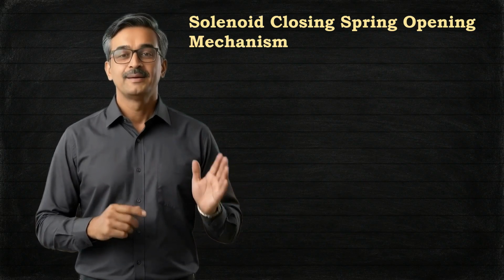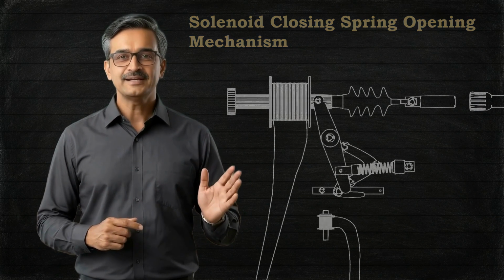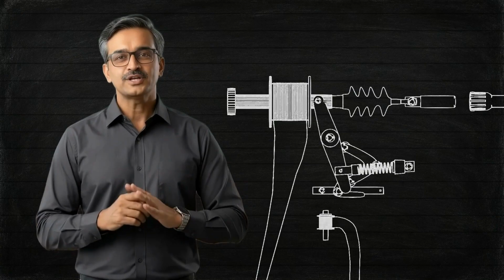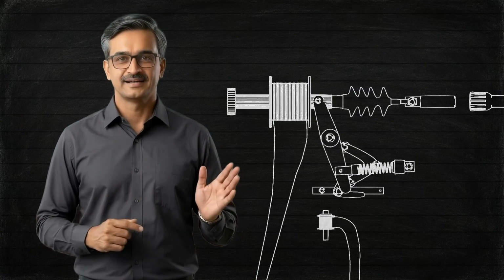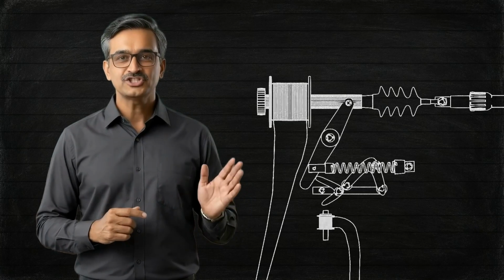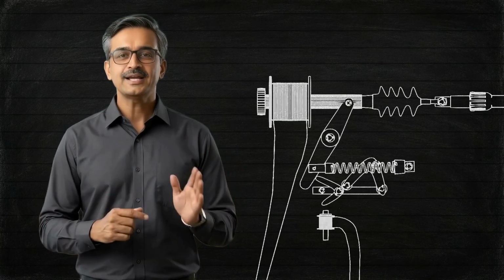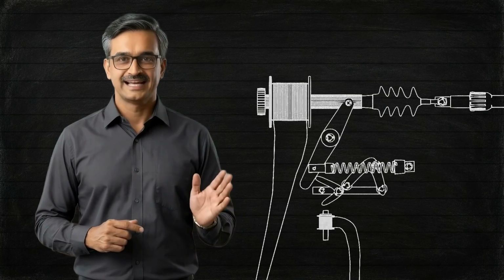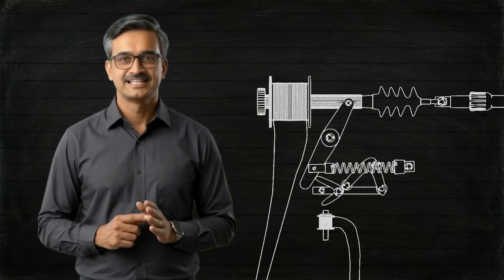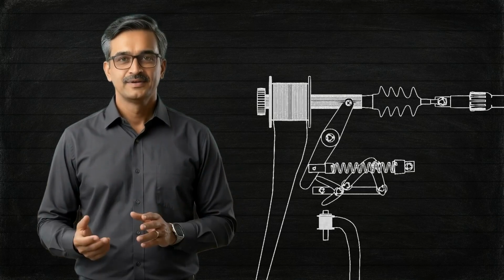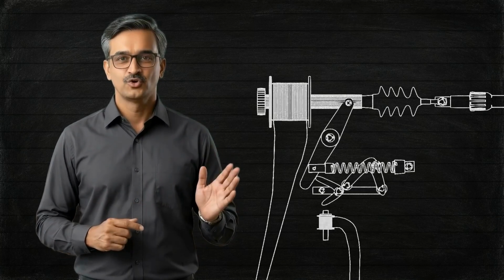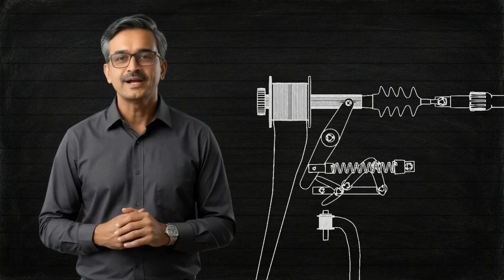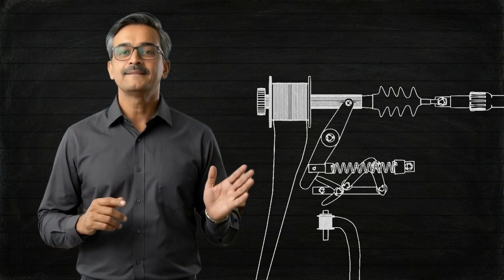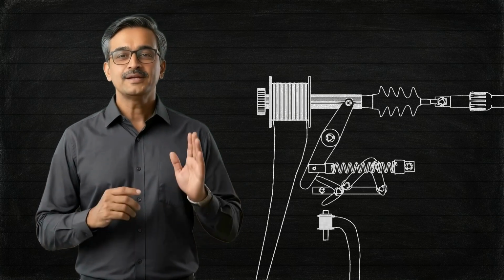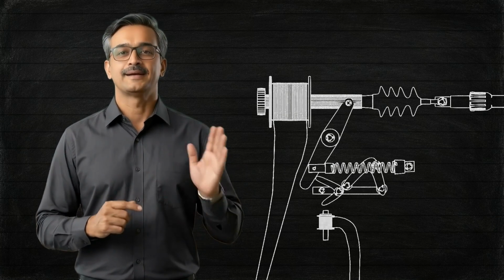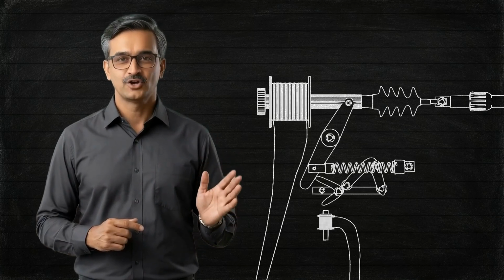Now we shall discuss the solenoid closing spring opening mechanism of a circuit breaker. This is an obsolete type of circuit breaker operating mechanism technology. Here, the plunger of the solenoid directly pushes the moving contact from its open position to the closed position. Thereby, it makes the circuit breaker close. Actually, we use an electromagnetic solenoid here. When we send a close command to the circuit breaker, we actually send DC power to the closing solenoid coil. As the solenoid energizes, it pushes its plunger, and that plunger is mechanically coupled with the closing mechanism of the circuit breaker. As a result, the circuit breaker closes.